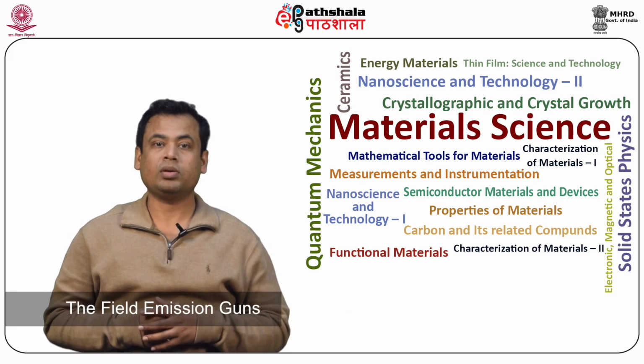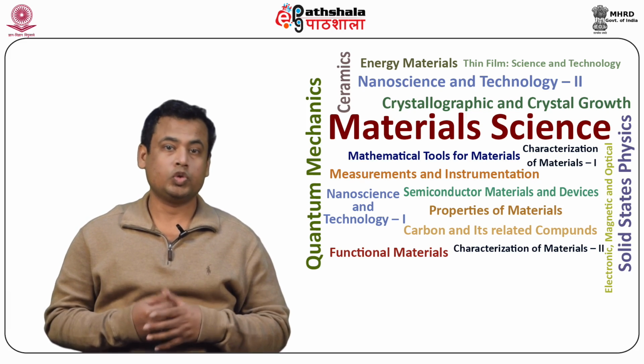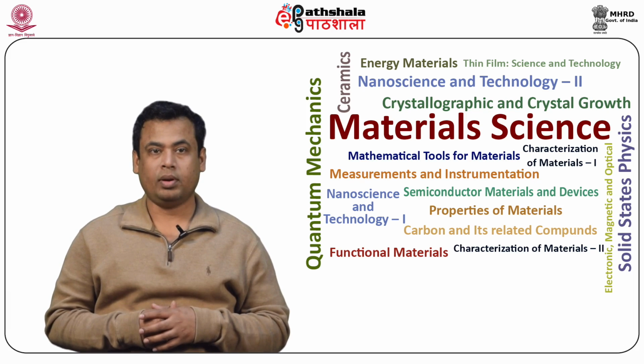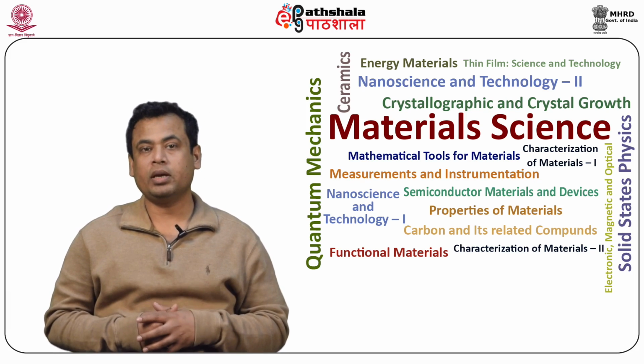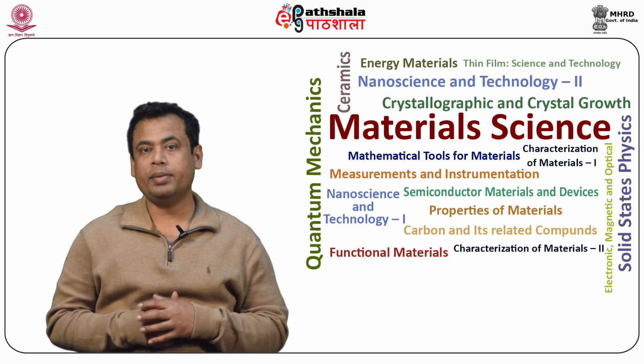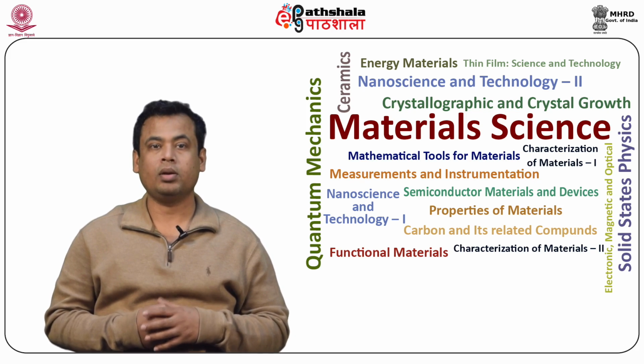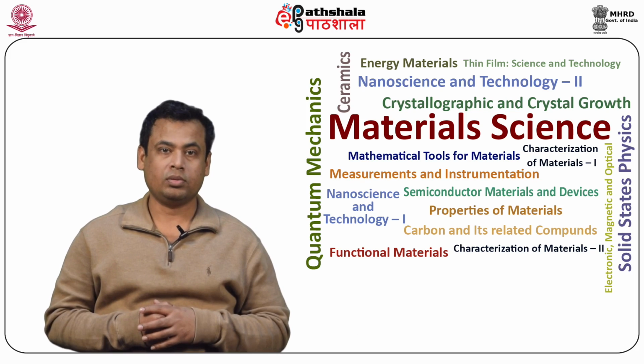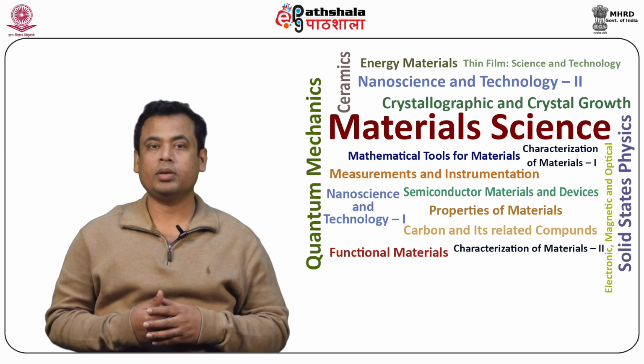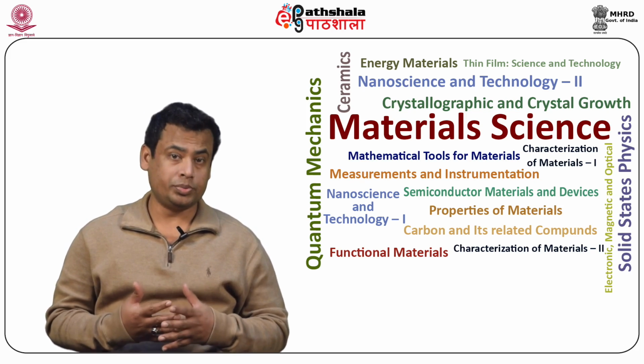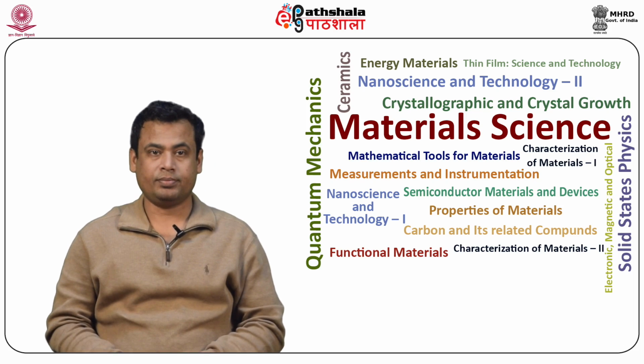The field emission guns provide superior brightness and higher spatial resolution than LaB6, and also their emitting surface remains clean during operation without adsorption of gas molecules.